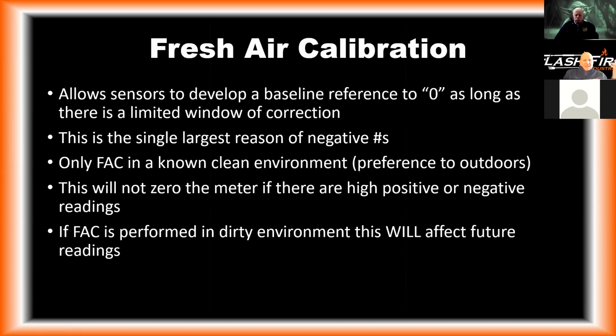So if I'm in 10 parts per million of CO and I perform a fresh air cal on the meter, it probably will take it, but now I'm going to be off by about 10 parts per million until I fresh air cal it again in a true clean environment.